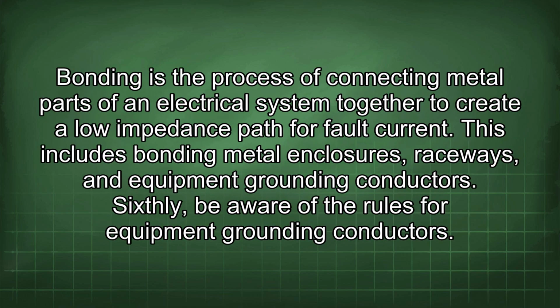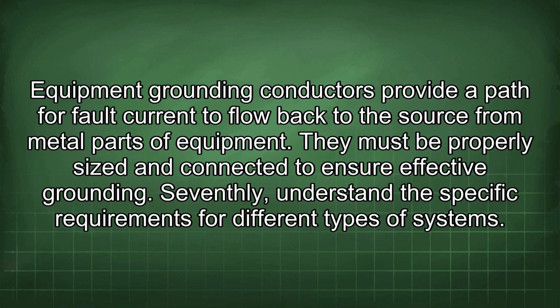Bonding is the process of connecting metal parts of an electrical system together to create a low impedance path for fault current. This includes bonding metal enclosures, raceways, and equipment grounding conductors. Sixthly, be aware of the rules for equipment grounding conductors. Equipment grounding conductors provide a path for fault current to flow back to the source from metal parts of equipment. They must be properly sized and connected to ensure effective grounding.